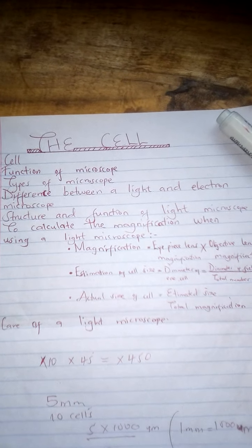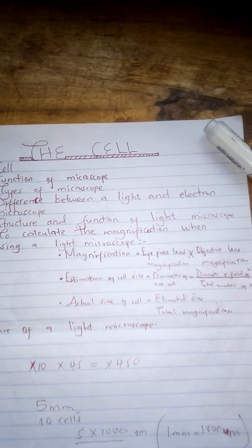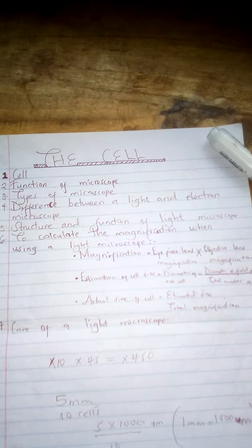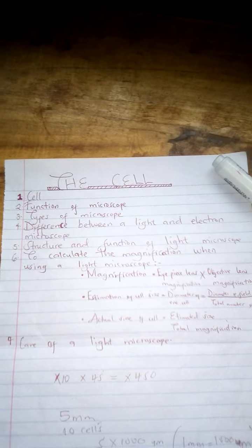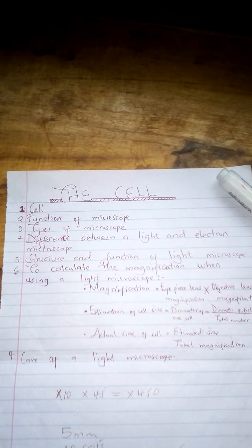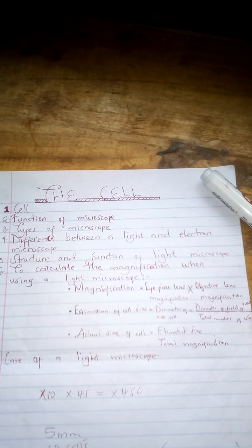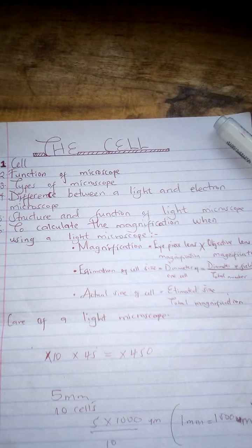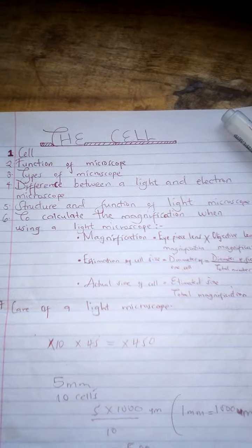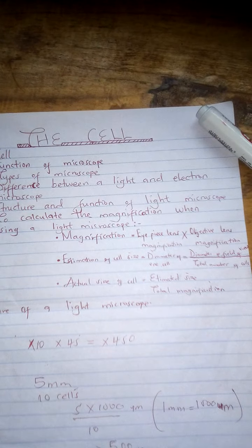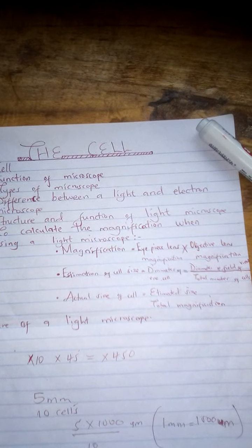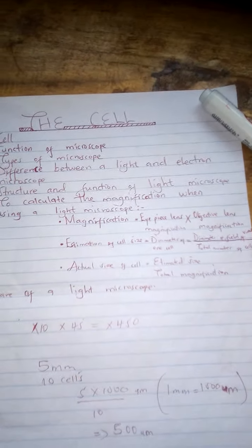Clean dirty lenses using special cleaning paper. Do not pour water on any part of the microscope. Ensure that the low power objective lens clicks in position after use. Store the microscope away from a dirty place, in a place where it's safe and free from moisture and even dust.